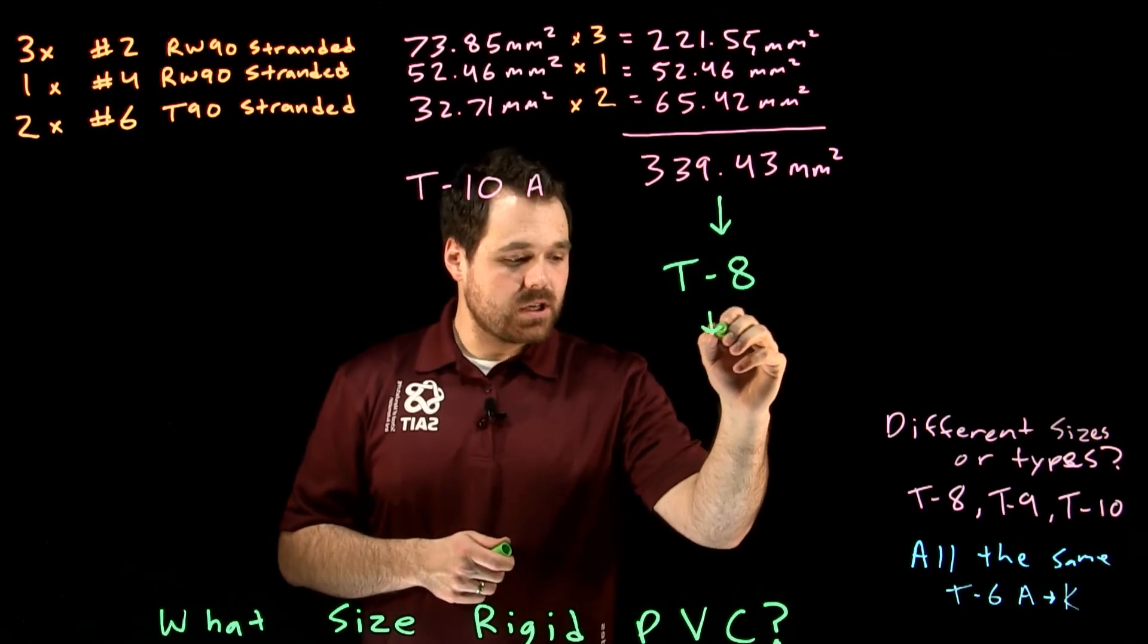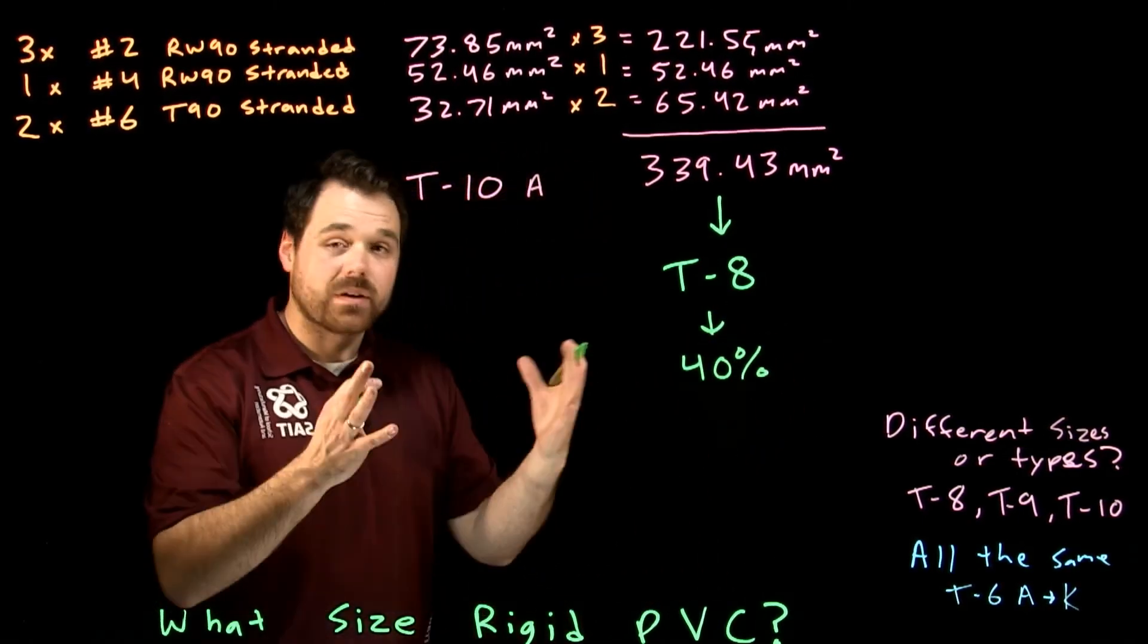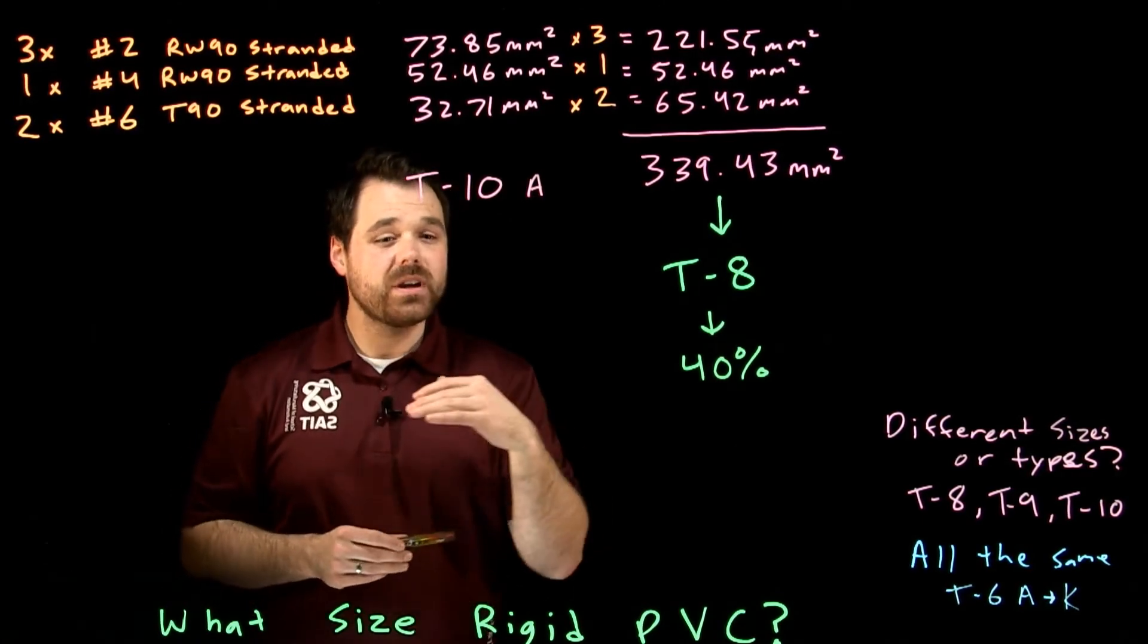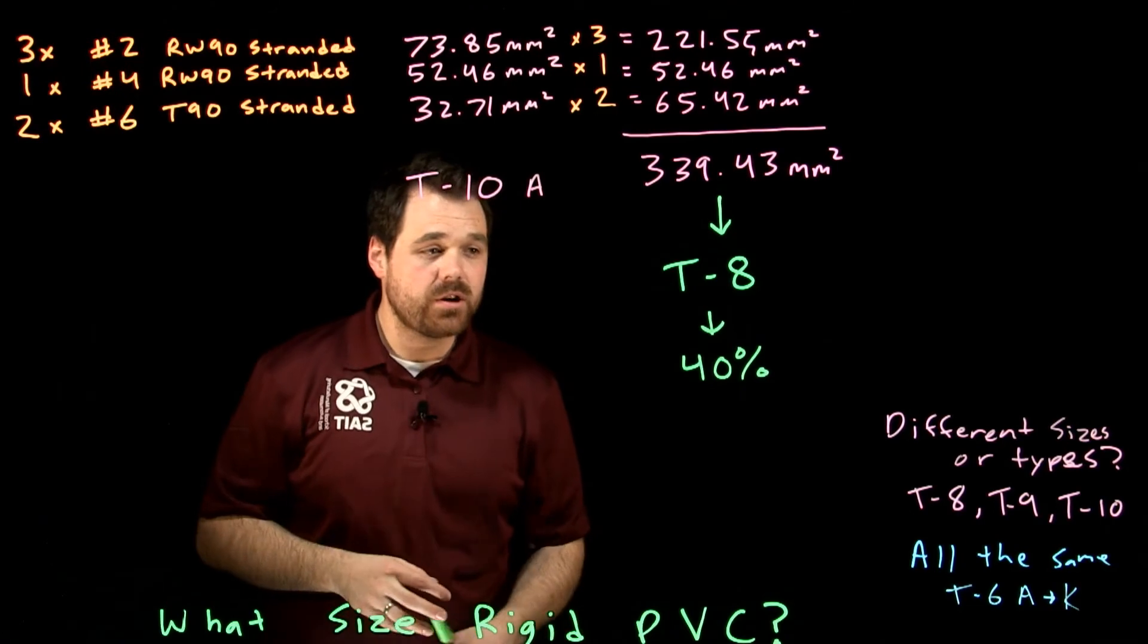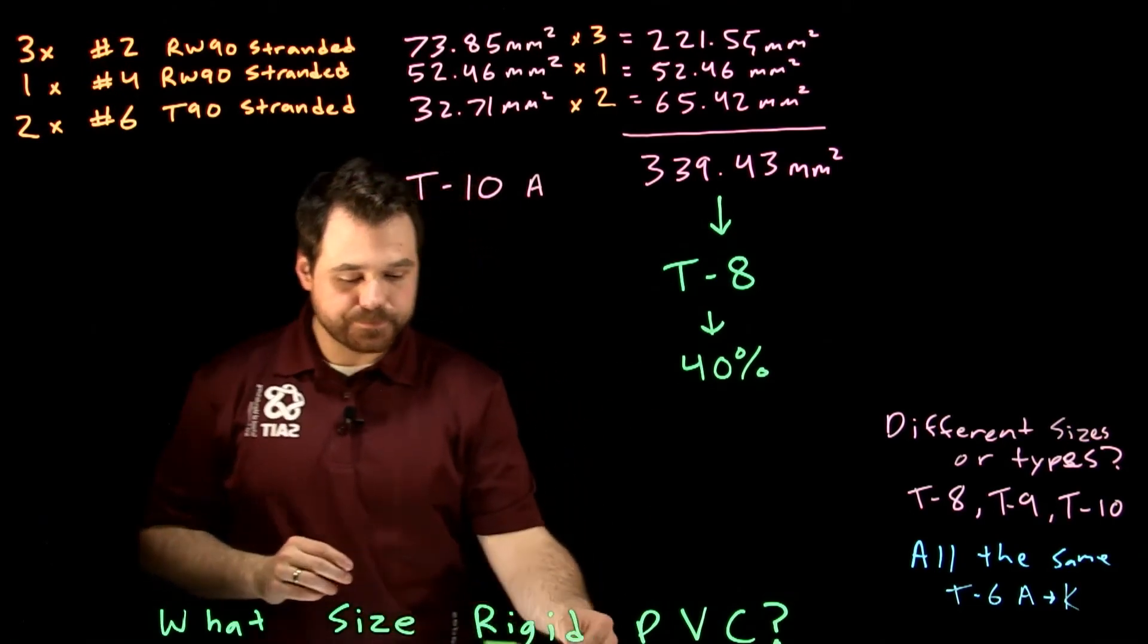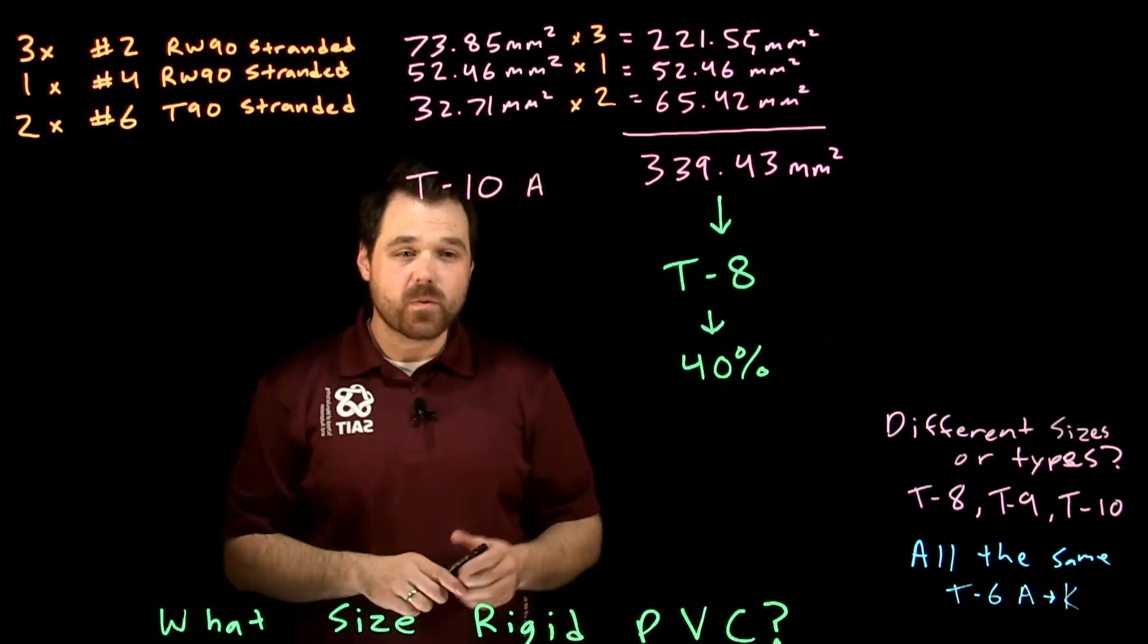So table eight, in this case, tells us we are going to use the forty percent column. Forty percent fill. We're going into the non-lead sheath and we have more than four conductors in our conduit. It tells us forty percent. Now, once we have this number, we take that forty percent.